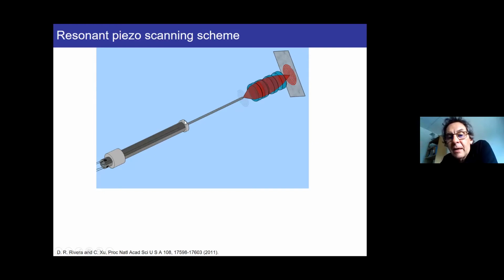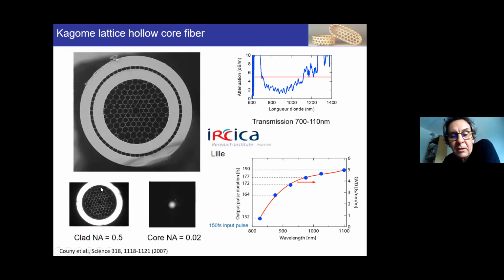But this scanning range is very weak. It's of the order of less than 10 micron. So in order to make the amplitude of the movement bigger, we stick our fiber to this piezo tube and we use the resonant frequency of this freestanding piece of optical fiber, that will shake. This is our hollow core fiber, the one I presented before, that is just glued to the piezo tube. And there is a micro lens system which will image the fiber tip down to the sample, into the head of the mouse, and then it will also back collect the fluorescent signal that will enter the fiber. And as you understood, it will be mostly collected through the double clad, this ring I presented to you before, right?